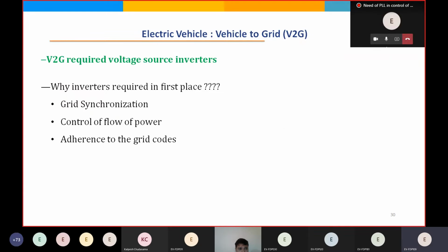Now coming to the voltage source inverter. PLL, phase lock loop, has a role to play in these voltage source inverters. So why are voltage source inverters required in the first place? One is grid synchronization — it has to do grid synchronization. It also has to control the flow of power, because a voltage source inverter has to control the flow of power from the DC link towards the AC side.